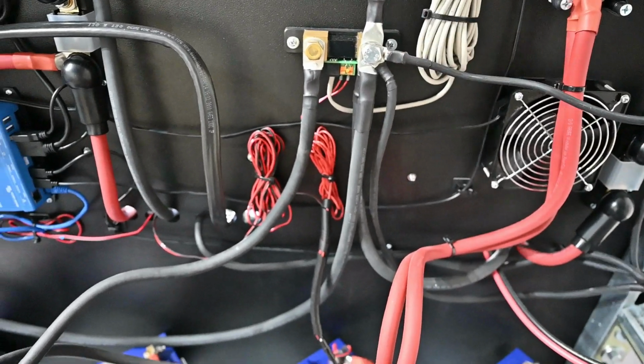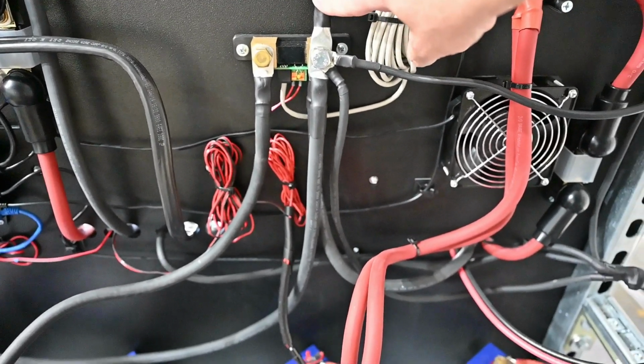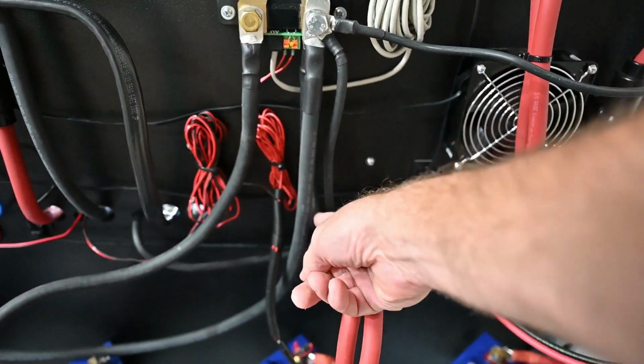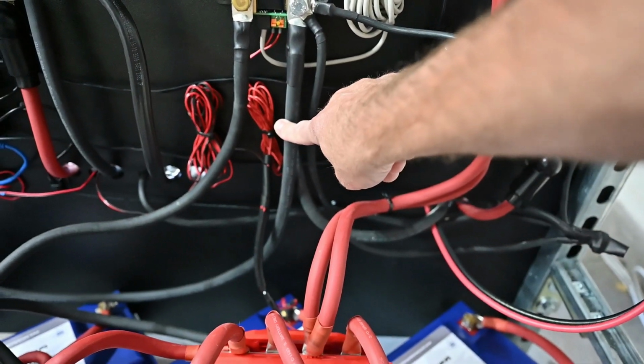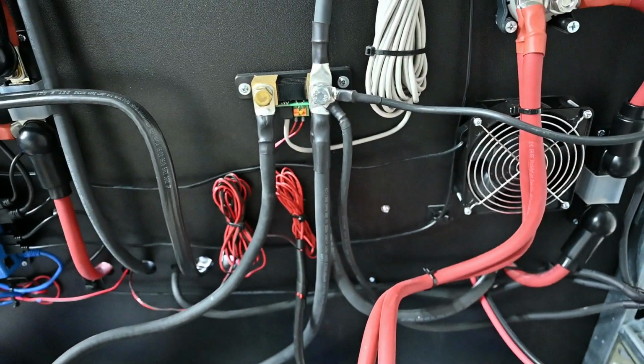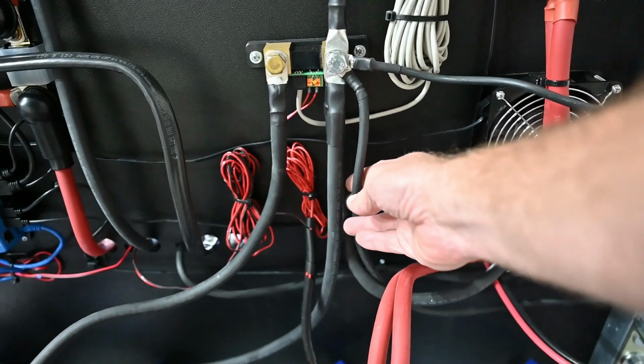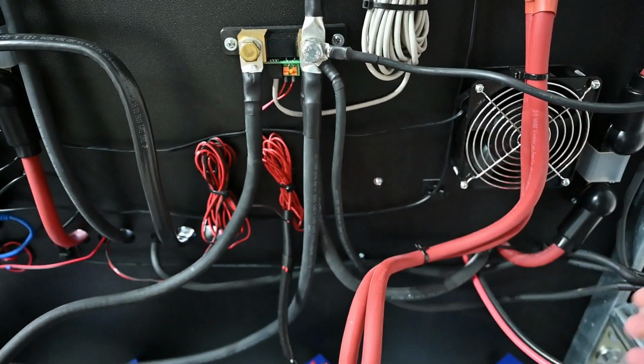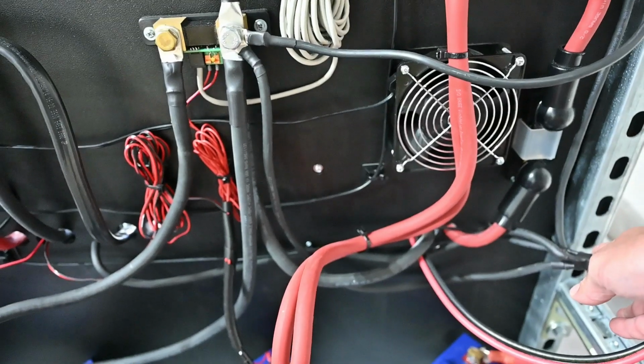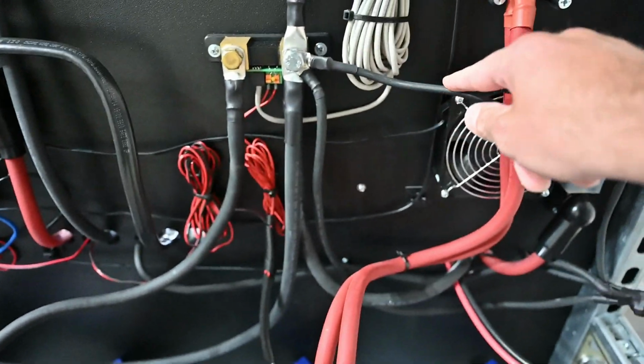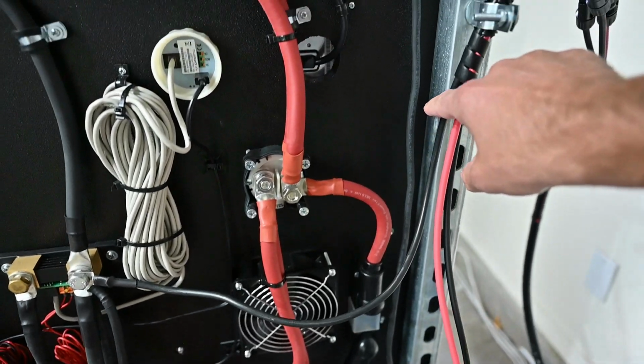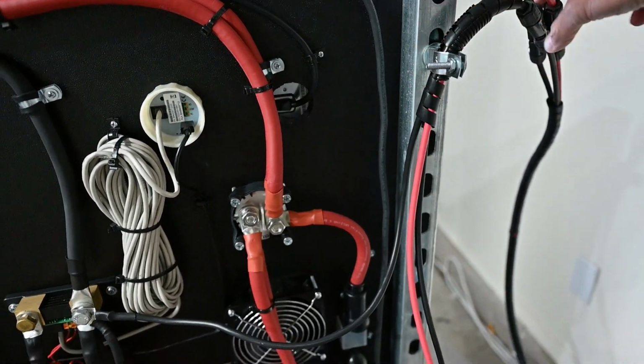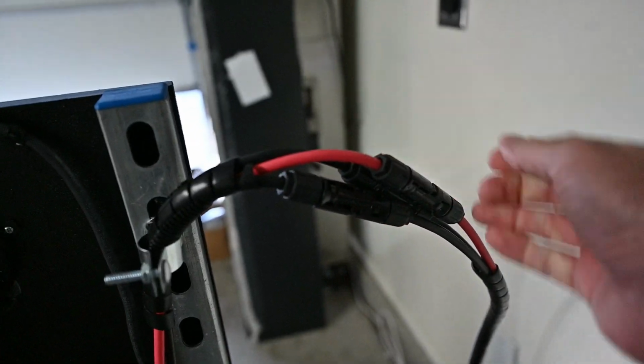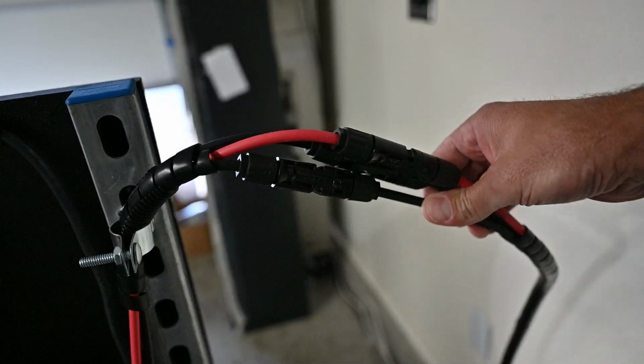You can see that an inverter is tied to ground here, the charge controller is tied to ground here, and the other inverter is tied to ground here. This particular cable is just a large cluster of equipment grounds, and this one is the system ground, which is connected with an MC4 connector to a copper rod in the ground, separate from anything in the house.